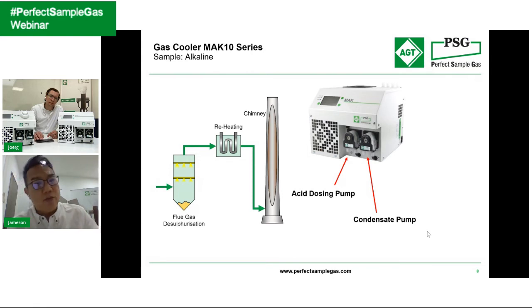So if you're measuring SO2 for efficiency, with the same gas cooler you can actually use one of the pumps as an acid dosing pump, to bring the flue gas back to acidic for that measurement. That means what we technically do inside the cooler is add acid into the measurement, so that makes the gas sample contain so much acid that it's not going to lose, or will only lose very rare components of SO2. Is that what you're saying?